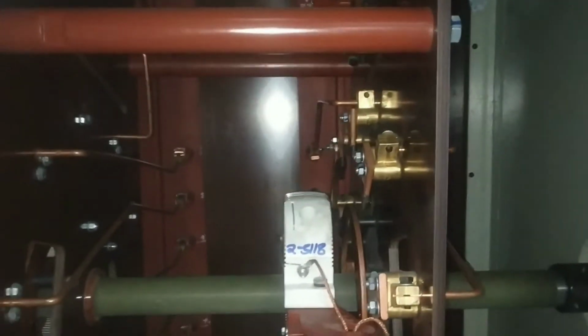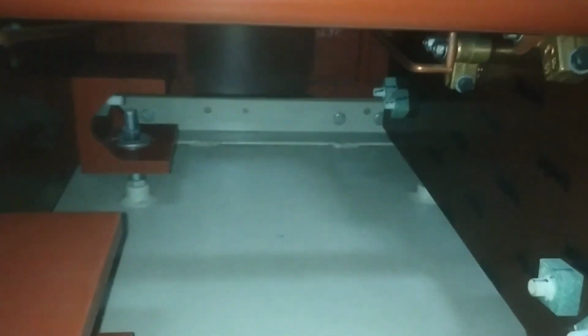This is the other side of the OLTC, and in this chamber the tap changing occurs. These are the shafts coming out from the control box, and each shaft is coupled through the gears. Also you can see that tapping connections are coming from the windings which will be connected to the tap position. The entire mechanism is fixed to a rigid body which will be holding this. In some OLTC, like oil type transformers, oil is being used within the OLTC chamber to carry out the heat generated during the tapping changes. This OLTC doesn't have any oil, and air is the only medium present within this.